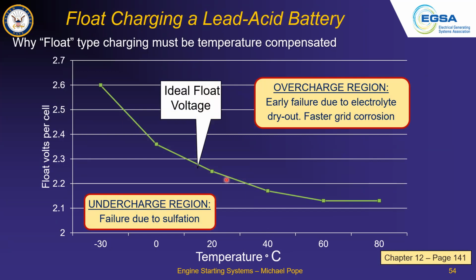Well, that's well and good, but the temperature is going to change, the ambient temperature. And as that changes, it alters the chemical reaction within that battery. So we have to be careful about the charge rate. If the temperature is cold, the chemical reaction slows down, so we have to increase the charge rate to compensate for that. The reverse is also true - if the battery is in a hot environment, then that chemical reaction is going to be accelerated, and we have to be careful that we don't overcharge it, or undercharge it.